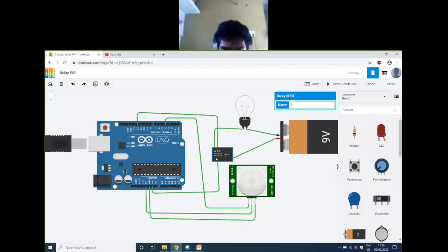Okay, see, here you have a relay. On this relay, it is written AC and DC. Whatever example I showed you in the slide is nothing but this relay. In this relay, 3 amps at 125 volts AC is there, and 3 amps at 24 volts DC. So if you want to use this for DC, you have a limit of 3 amps load with 24 volts maximum voltage.